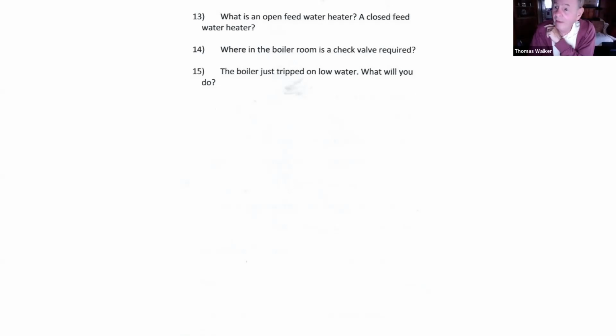Excellent. And the question they love to ask: the boiler just tripped on low water. What will you do? Shut it down. It's already off. Yeah. You've got to add water to it, but you let it cool down. No, you're going to troubleshoot the cause of the problem, and you're immediately going to add water to it. Would everybody agree with that? Yep. And once you've established the normal water level, what are you going to do? Restart the boiler. Restart the boiler.